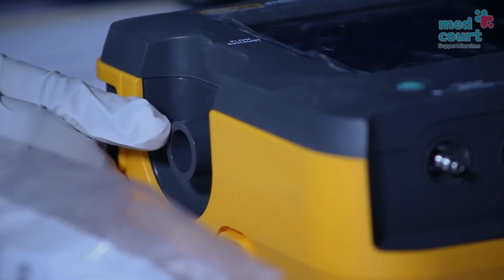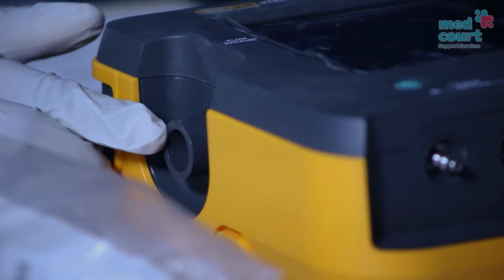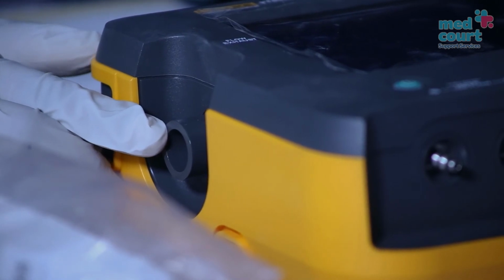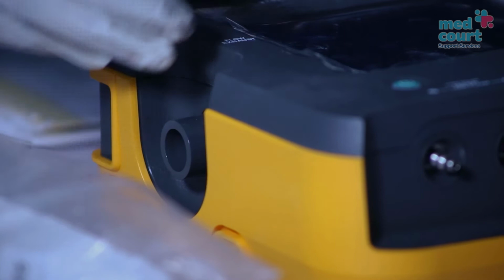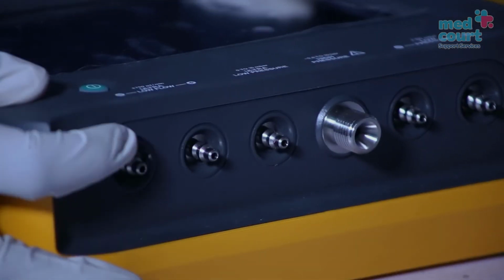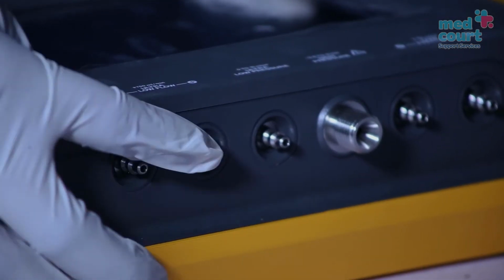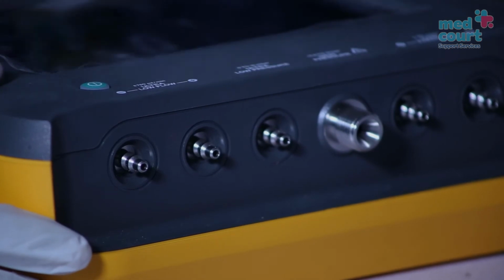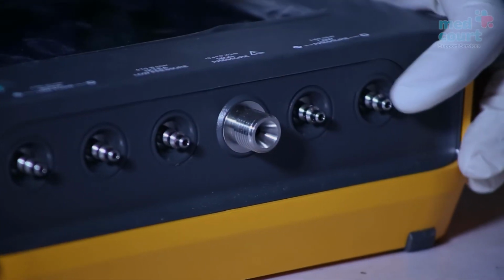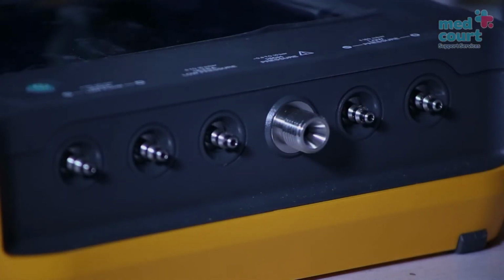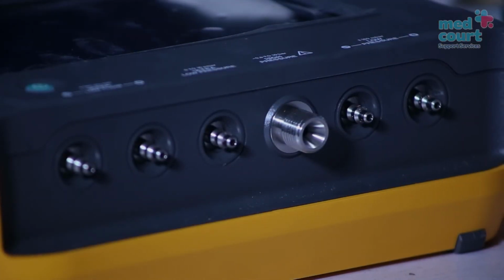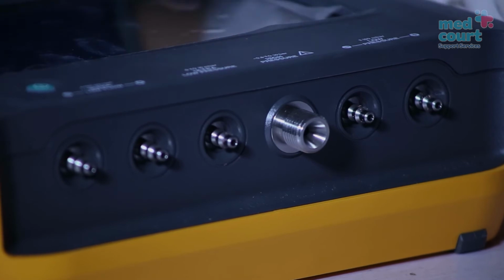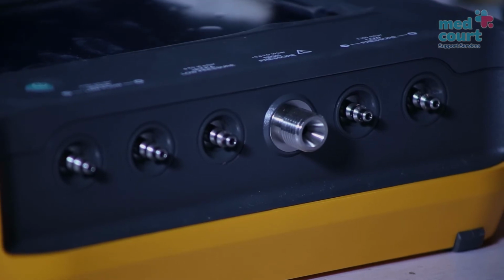The VT900A has a single flow channel, which comprises the flow inlet and the flow exhaust. There are also several ports: the ultra low flow, the ultra low pressure, the high pressure, and the low pressure ports. The high pressure port uses the standard DISS oxygen connector and is used to connect to gases in pressurized containers. The other ports can be used on gas flow equipment such as oxygen concentrators and anesthesia machines.